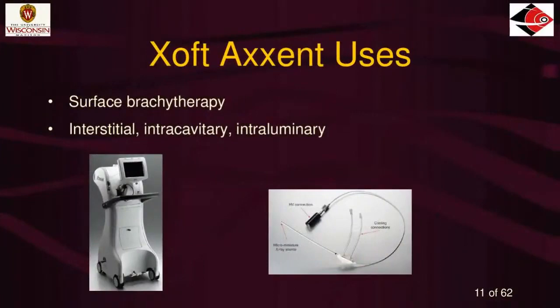These EBT sources can be used to treat skin as surface brachytherapy, or placed inside a patient for interstitial, intracavitary, or intraluminary treatments. The Xoft system is mobile and wheels around your department. The X-ray tube connects to cooling connectors and a high-voltage connector for the 50 kV generator. These are disposable sources — the manufacturer has recommendations on how many patients and uses they're meant for, and they are not permanent sources.